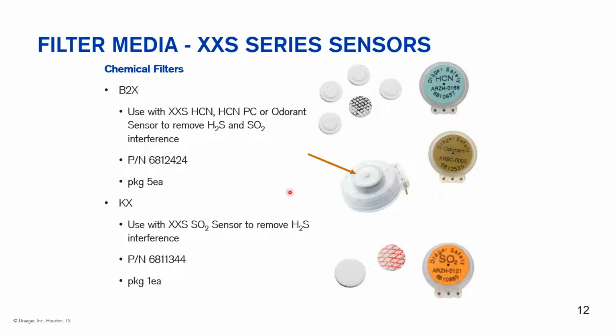And very similar with our new XXS series of sensors, we do have a number of sensors that have filters that can go on the inlet of those sensors. So again, we can filter out some of the cross interferences, but when that filter again gets saturated, we can replace the filter and not have to replace the whole sensor.